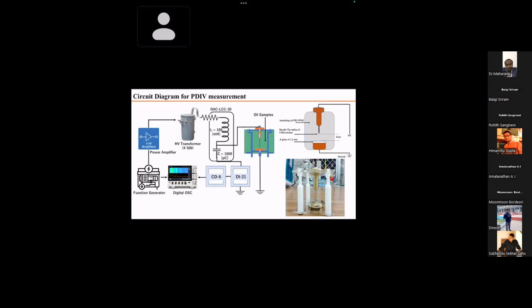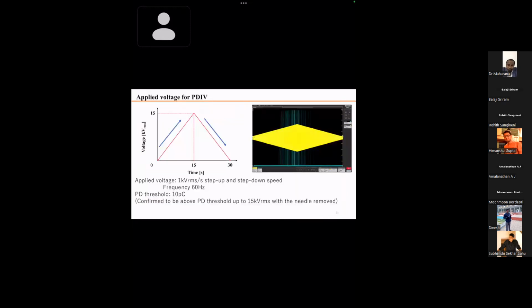For the partial discharge measurement, you showed PDIV and PDEV, and the change between them is not much. So when you increase voltage to check PDIV and then decrease to zero with the same decrement, you see a drastic reduction—you don't get PD below a certain level. For example, in the first row you see partial discharge at 11.5 kV, but coming down, you don't see any PD less than 11 kV. Is that correct? Yes, correct.